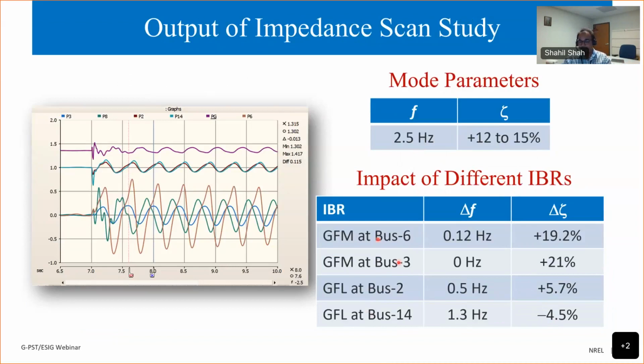We can find out how these different IBRs are impacting the modal frequency, as well as, more importantly, the damping. One thing I would like to highlight is that some system operators I have seen consider that if the oscillation is high at a particular IBR, that IBR is possibly a negative contributor causing the oscillations, and they try to curtail it. But here, the oscillations are high at the IBR at bus 6 compared to other IBRs like this grid following one, yet the IBR at bus 6 is actually contributing positively.